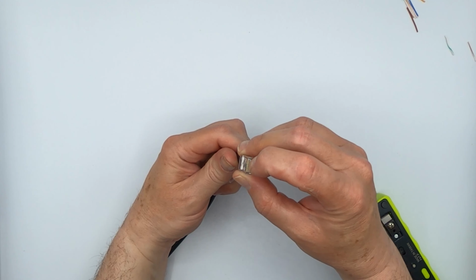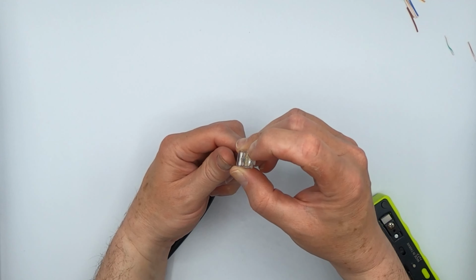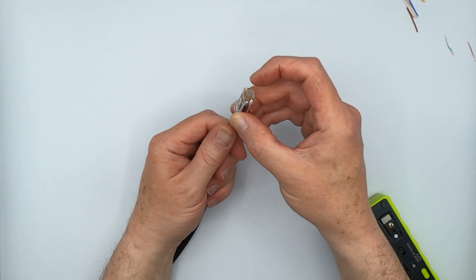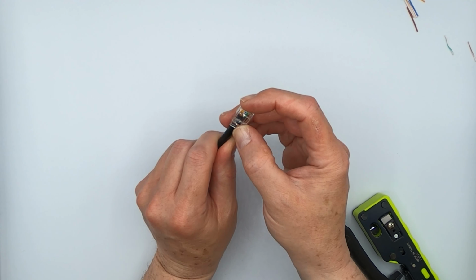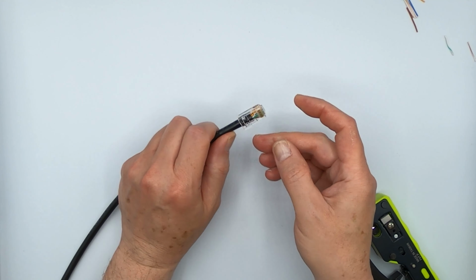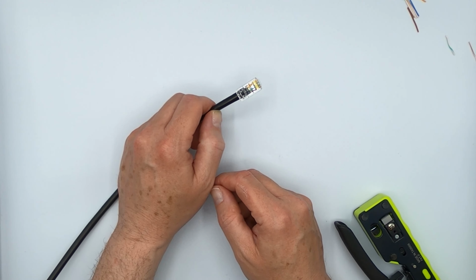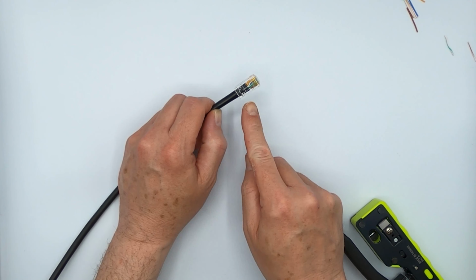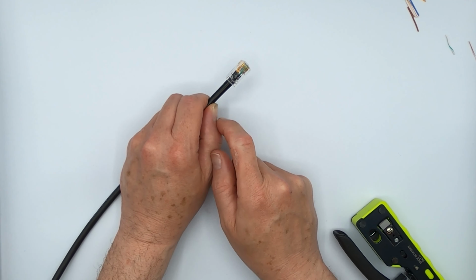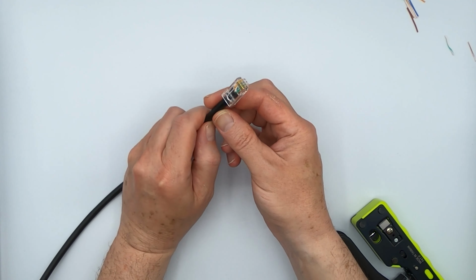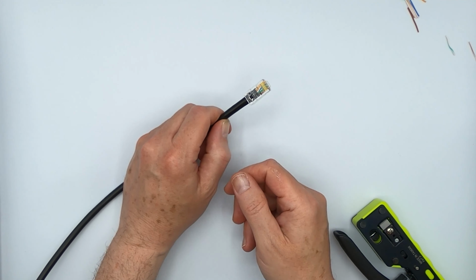Check to make sure the golden contacts are fully seated and that the conductors are fully flush cut off, and they are. So there you go. We've got a perfectly good termination. All the contacts are down, the cable jacket is pretty far up there, and this is a great termination to go ahead and plug into something.